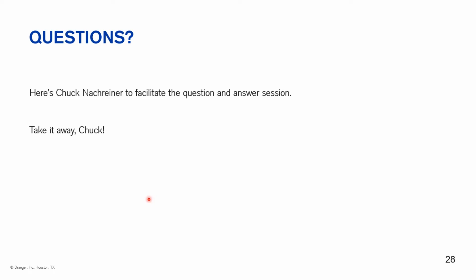Okay, and you would do that prior to every use? Well, by legal definitions, we do recommend testing a unit prior to use. In the real world, that doesn't always happen, but test it prior to use or test it as often as you can just to make sure. If it's been dropped in mud or water or suffered a severe shock, we do recommend doing a quick test after any physical impact, just to make sure everything's still working as it should.